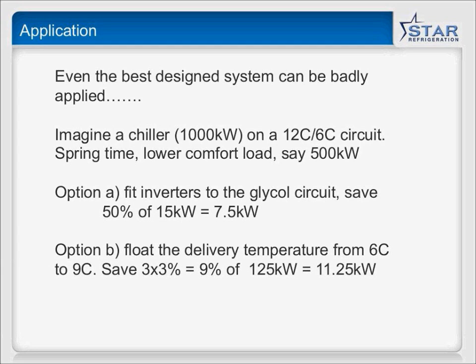Here's a really good rule of thumb. Every degree that you change the operating conditions of your plant, whether that's on the cold end or the hot end, makes a 3% change in its performance. If you widen that temperature difference by 1 degree, you make it 3% worse. If you narrow it, you make it 3% better.